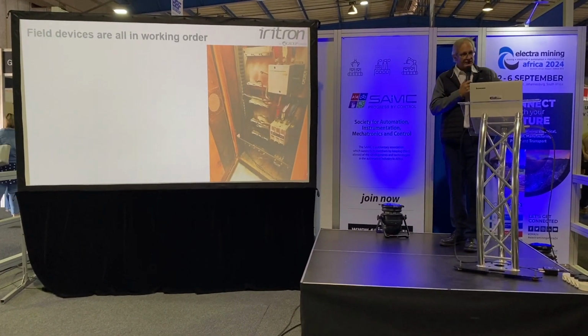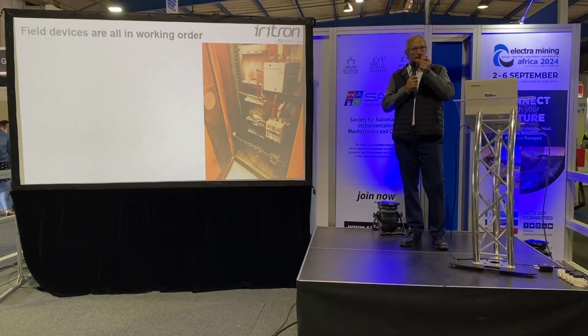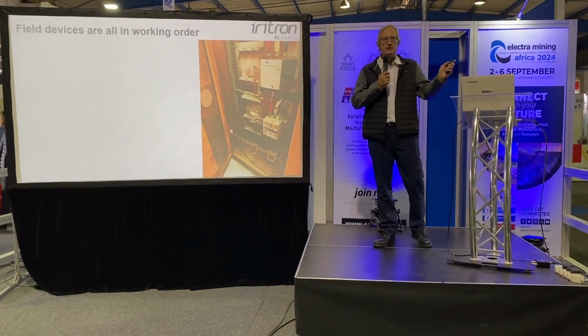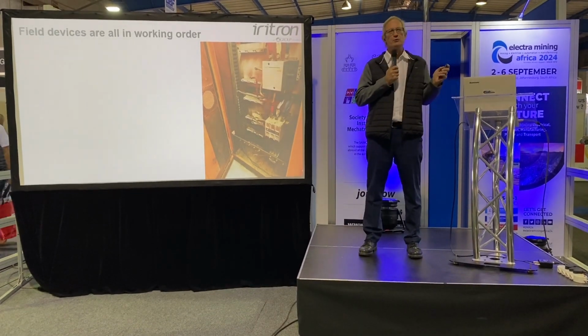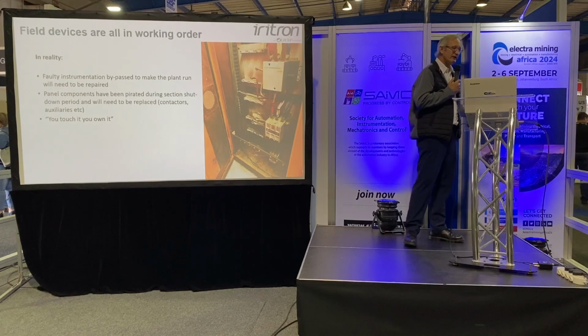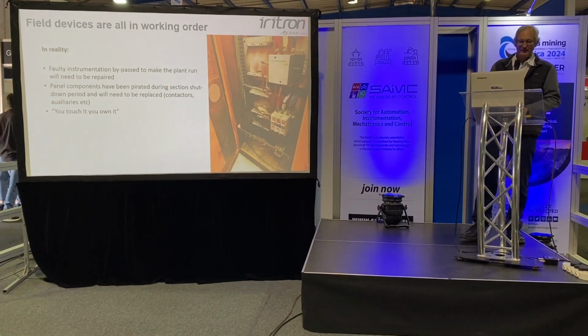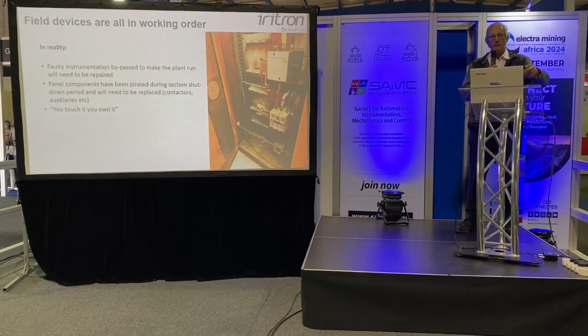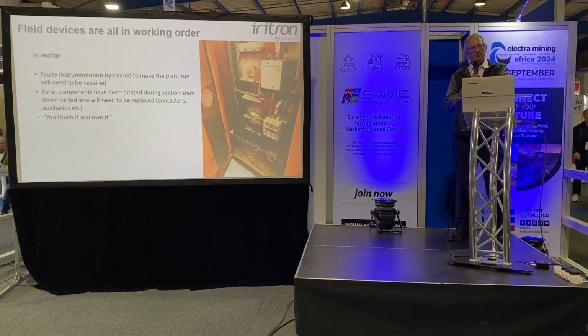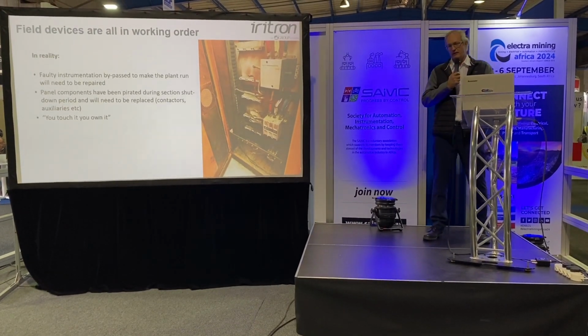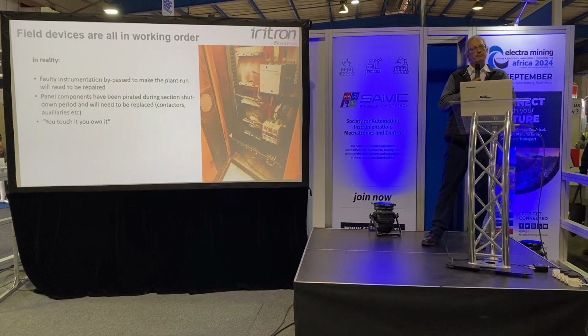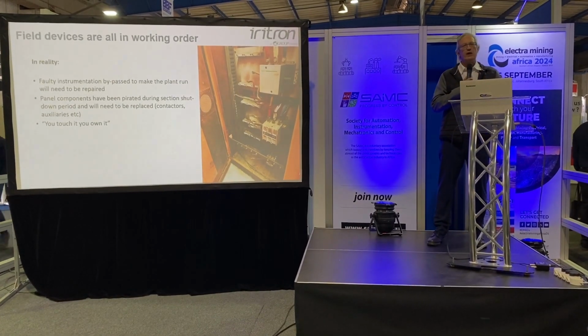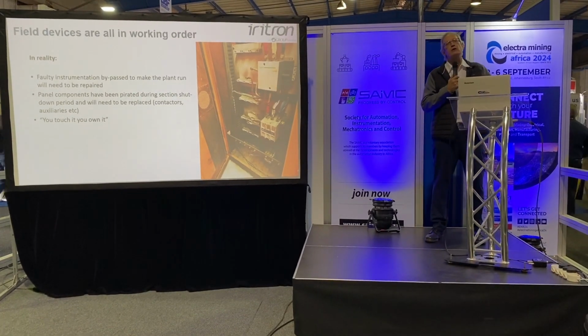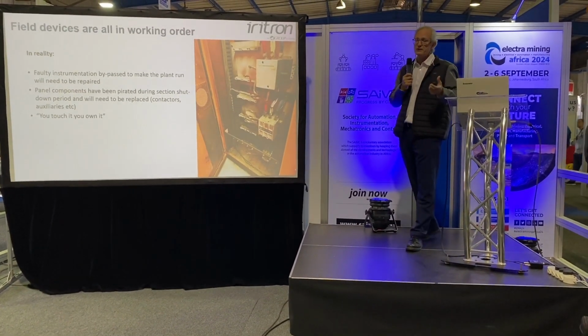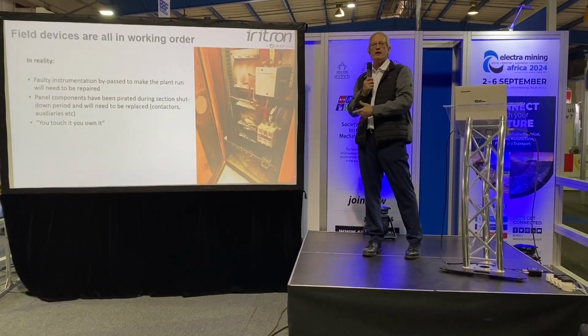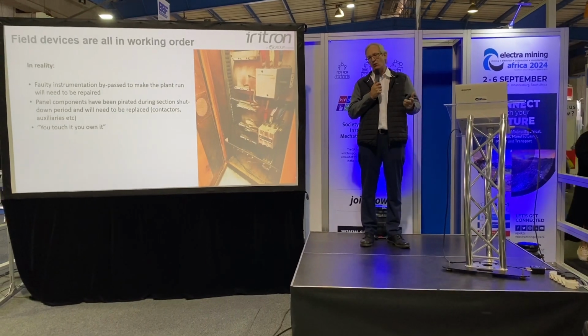Which brings me to the next one, which is that the field devices are all in working order. When we switched off the plant 3 months ago, 3 weeks ago, everything was working. In reality, it's not always the case. Faulty instruments are bypassed on the plant floor to make the plant run. So the sequences can start up, the plant can produce products, because we've actually bypassed some instruments. We don't have a spare instrument, so we bypassed it to get the plant working. The bypass can be physical, in the field, or in software, in the PLC or in the SCADA.